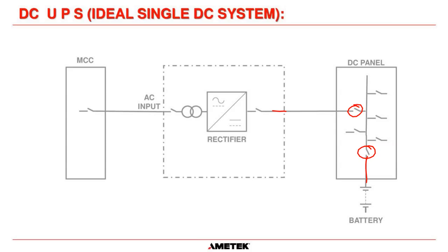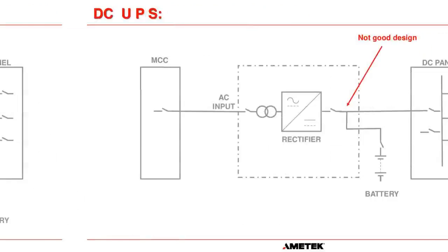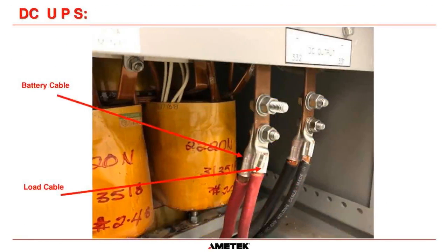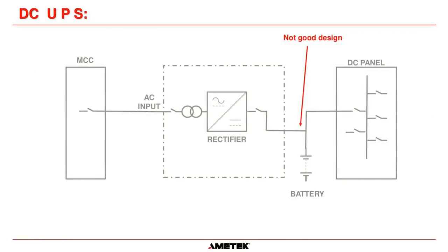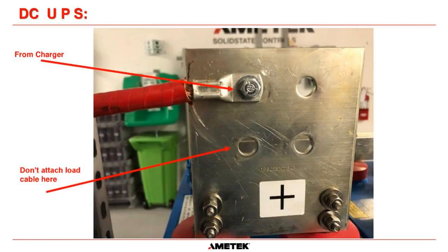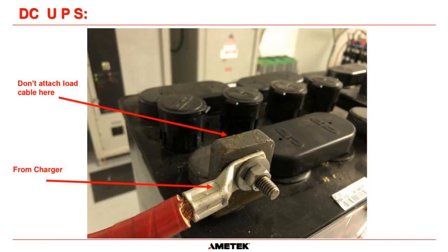So it will require some engineering, and it will probably require a load outage, although there are ways and means around it, but it usually means you have to tie in either a temporary charger or a temporary battery into your system while the system is hot. So it can be done, but it does introduce some safety issues, which could cause some problems, but it can be done.